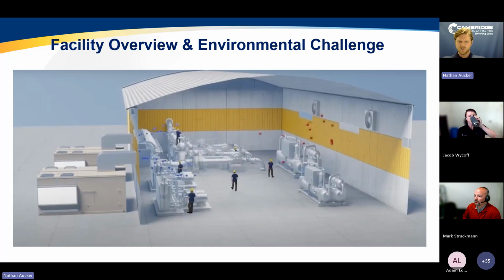This equipment uses a plate heat exchanger with outside airstream. In drier climates, even, it can be more effective as well. And one of the tremendous benefits of this equipment is that you already have the ventilation needs. So this is really a ventilation driven piece of equipment, and you're really trying to just knock some of the difficulty of the outside air conditions off, so the load to the building is just slightly less. No mechanical cooling needed, very energy efficient, and this can be a tremendous savings for the customer from an operation standpoint, from an overall cost of both install and then operation.